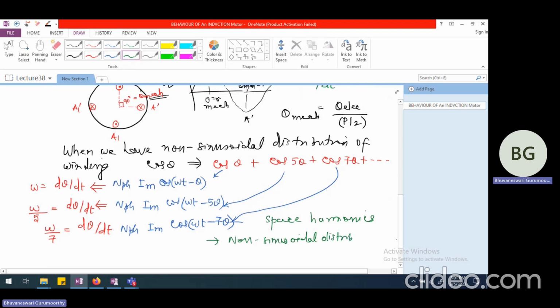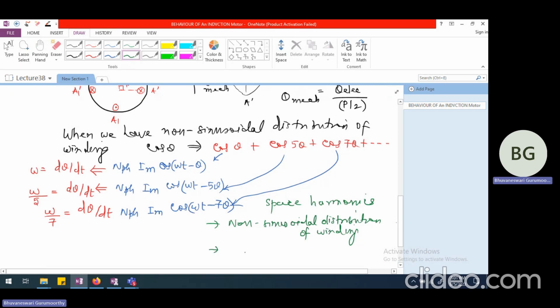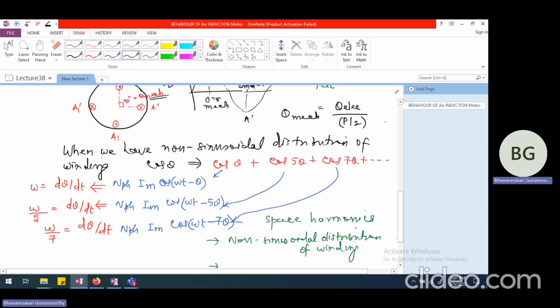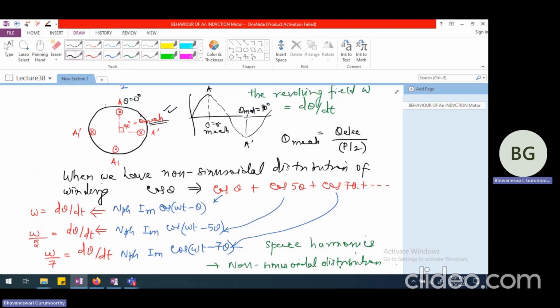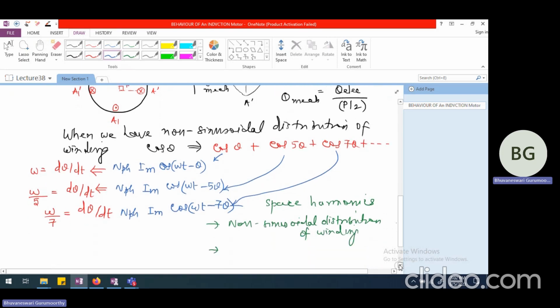Distribution of winding is the second reason, due to some kind of saturation near the slot. If you look at the teeth, the stator outer periphery has slots somewhat like this. This is one tooth, this is the second tooth, and between the teeth you have the winding arranged, coming in the slot. So due to the slot and teeth, there will definitely be some non-uniformity in the flux distribution.